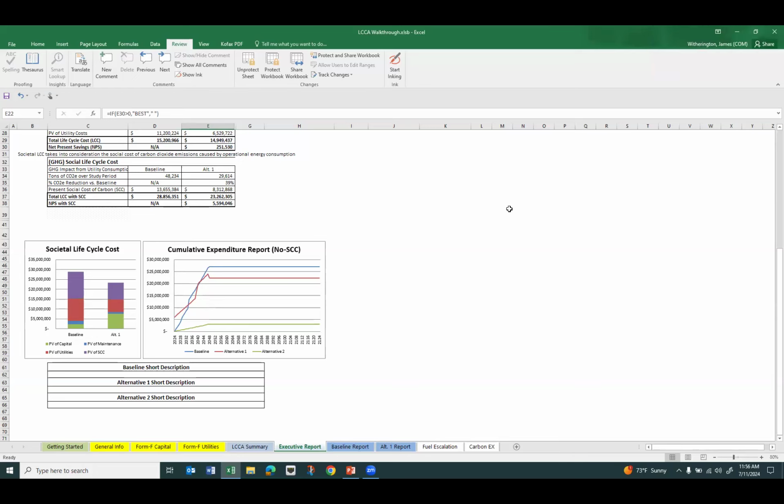Yeah, I'm just thinking of a scenario where somebody has a boiler that is probably going to need to be replaced in the next 5 years. But if you just look at the simple payback, it has like a 66-year payback. So it potentially might pass the LCCA, but wouldn't pass that initial simple payback.